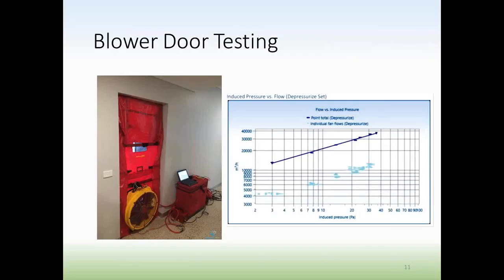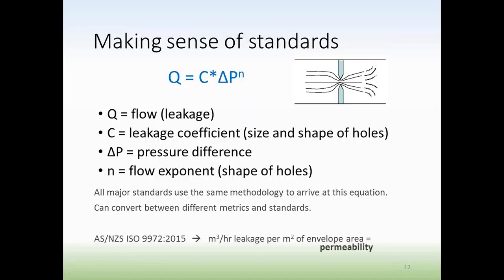So blower door testing, the concept is pretty simple, and that's why it's widely used. You use a fan to pressurize or depressurize the building, and you pressurize it to different levels. This chart here shows 3 to 40 pascals. Normally, almost all the test standards say you need to test the building up to 50 pascals. So you take a bunch of pressure measurements, and then a bunch of flow measurements through the fan, and you get a relationship between flow and pressure.